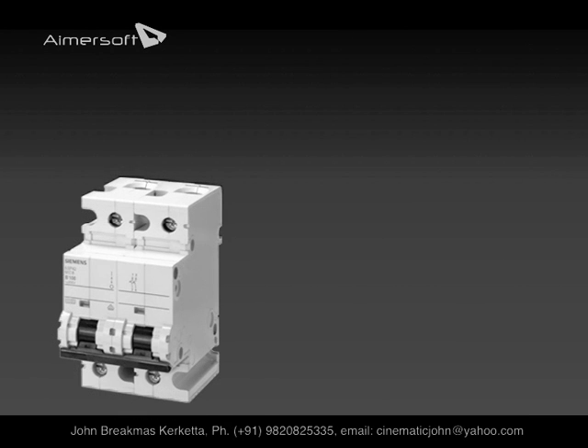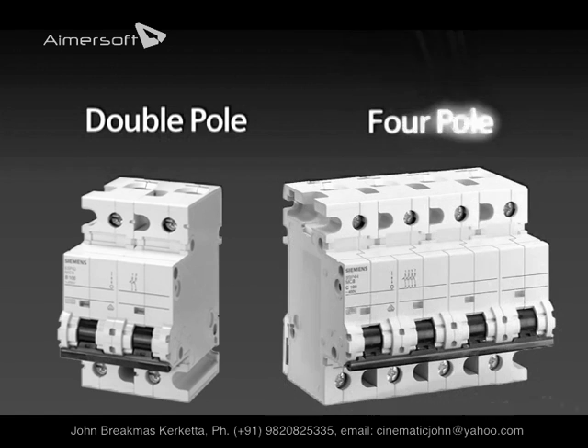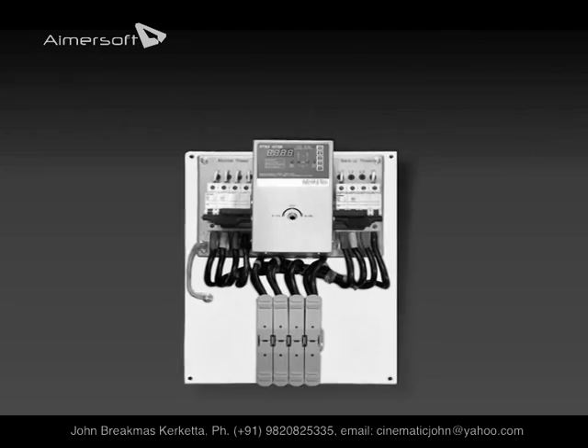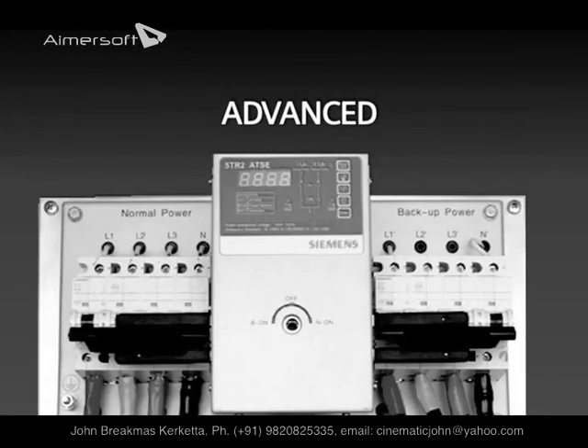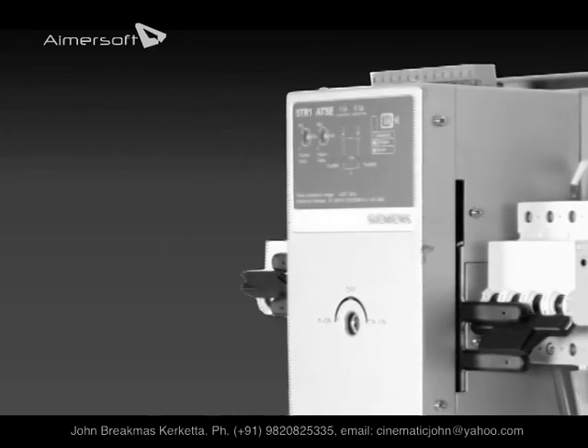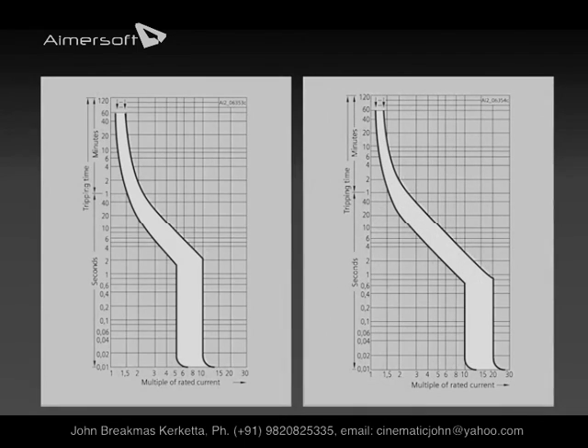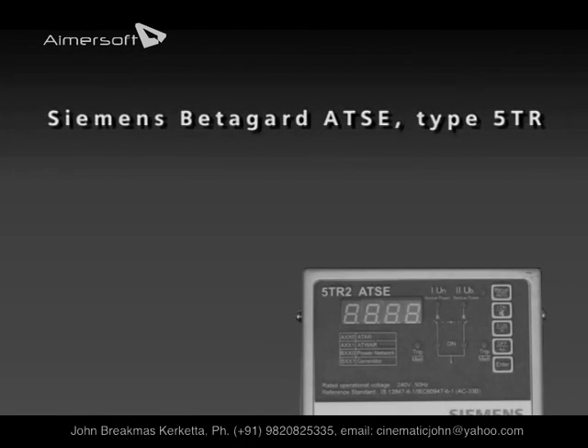The ATSE conforms to the international standard IEC 60947-6. In the Siemens Betagard ATSE, the switching devices used are miniature circuit breakers — MCBs — from 40 ampere to 125 ampere, available for both single phase and three phase power supply systems. Based on customer requirements, there are two types of ATSCs: the basic and the advanced. Customers also have a choice to select ATSCs with either C or D characteristics of MCBs.